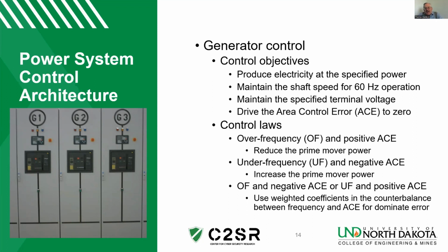Another control law is if we have under frequency and negative area control errors. That means we don't have enough power being generated, and so we increase the set point on the generator to provide more power and more speed. The real challenge comes when we have mixtures, such as over frequency and negative area control errors, or vice versa, under frequency and positive area control errors. In this case, we have to weigh in the various components to find out which direction we need to take the generators.